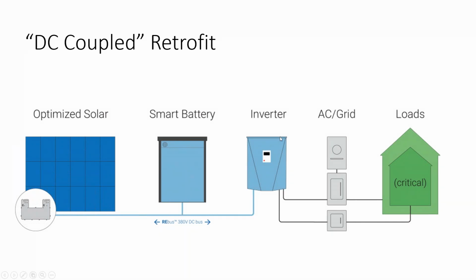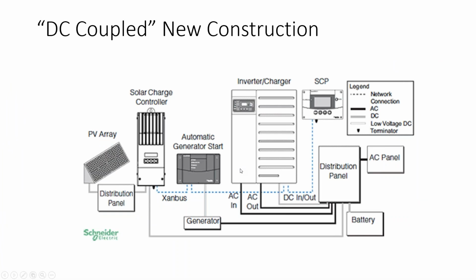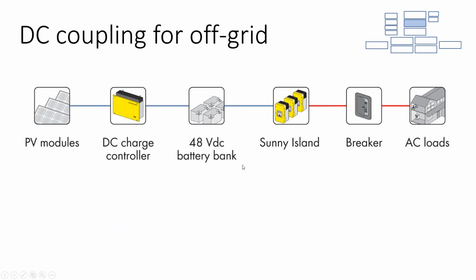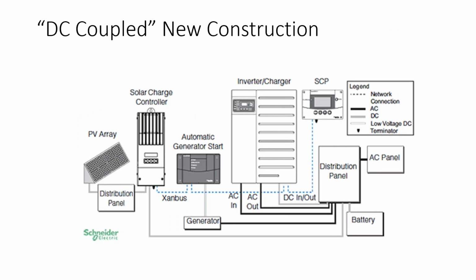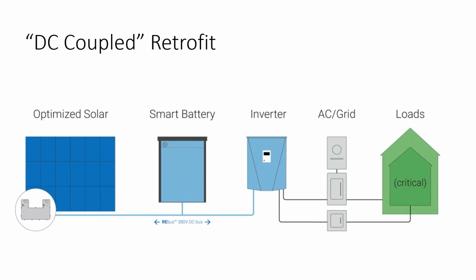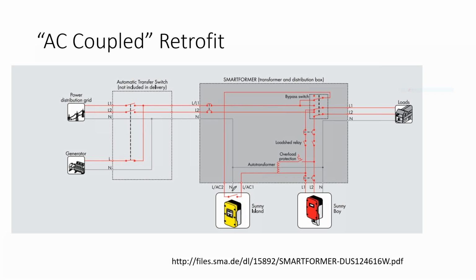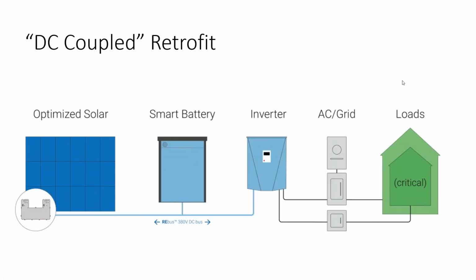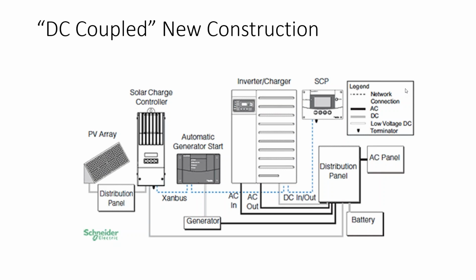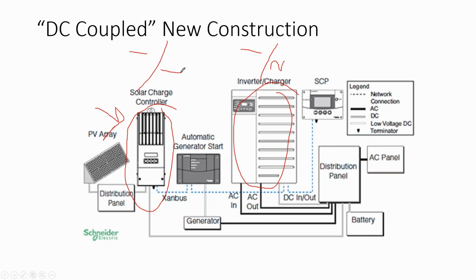So that begs the question, which is more cost effective - a DC coupled solution versus an AC coupled solution? Well, in an AC coupled solution, you have to buy two inverters. And the charge controller, regardless of its type, does not have all of the parts that an inverter has. An inverter does a DC to AC inversion, whereas a charge controller just takes the DC and converts it to another DC voltage. So the charge controllers are cheaper than inverters.